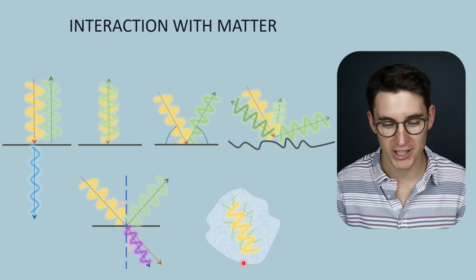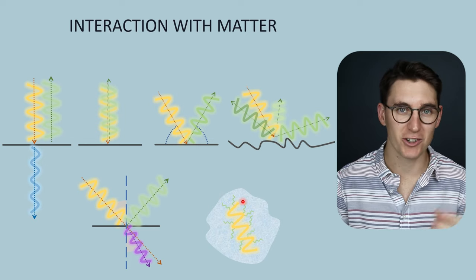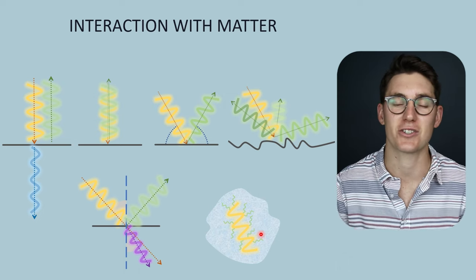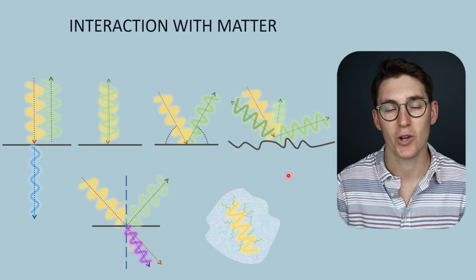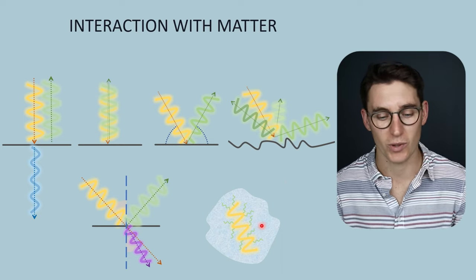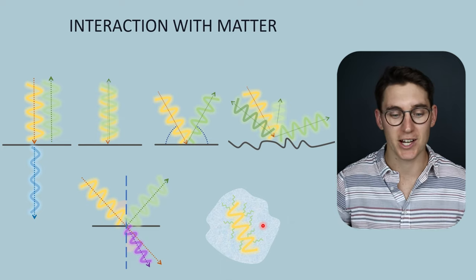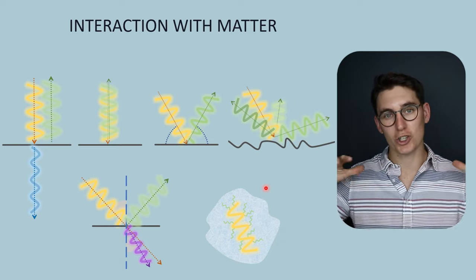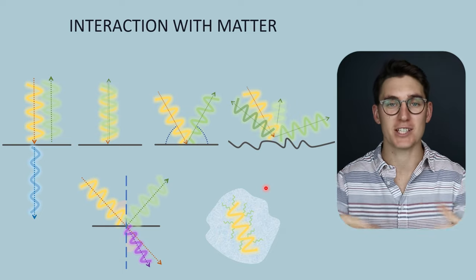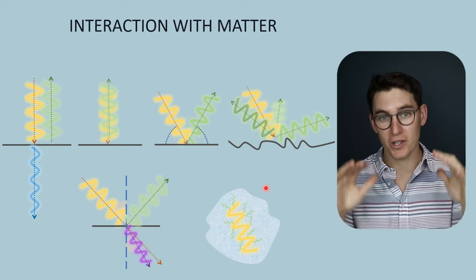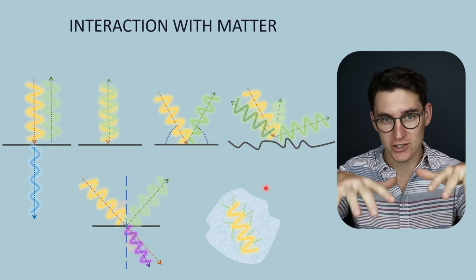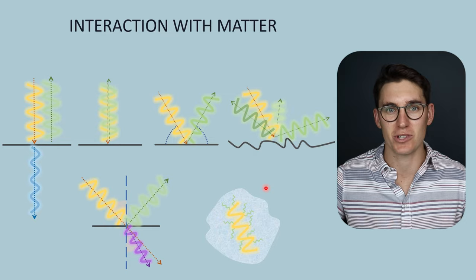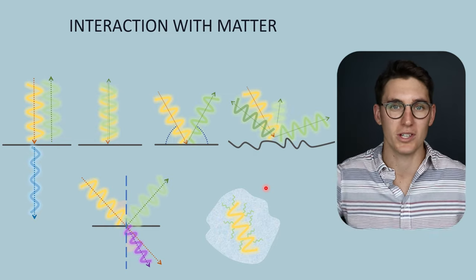The last type of tissue interaction is known as scattering. When an ultrasound wave interacts with units within a tissue that are smaller than the wavelength of the incident ultrasound wave, we get scattering — a loss of energy of the incident wave, with small sound waves produced in any direction. I like to think of scattering as a large wave in the sea coming towards a beach made of pebbles. Those pebbles are much smaller than the wavelength of the wave, and as that wave crashes in, it disperses in all directions. The energy is dissipated into lots of smaller waves.